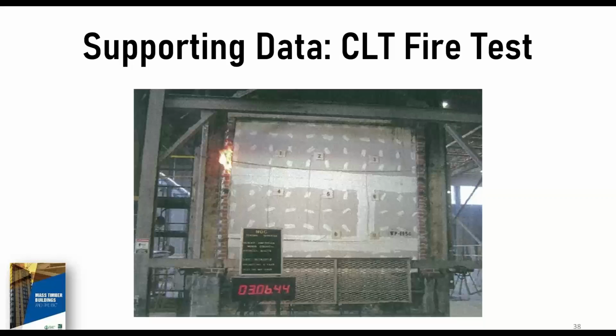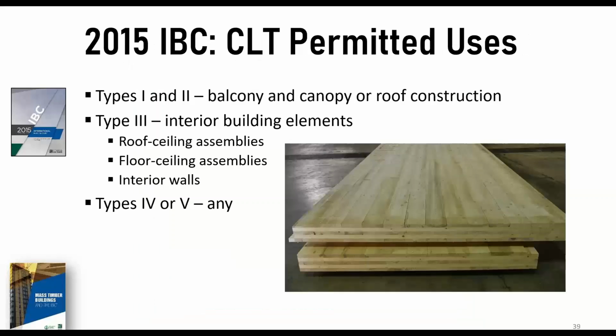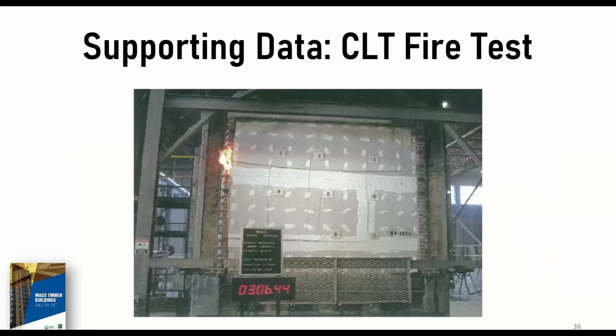We were shooting for a 2-hour fire resistance, and the assembly that was tested was a five layer thick CLT panel with 1 layer of 5/8 type X gypsum wallboard on the inside, and 1 layer of 5/8 type X gypsum wallboard on the outside. Again, they were going for a 2-hour fire resistance. You can see the assembly is starting to bow here. The test laboratory was able to apply 87,000 pounds of load to the assembly.